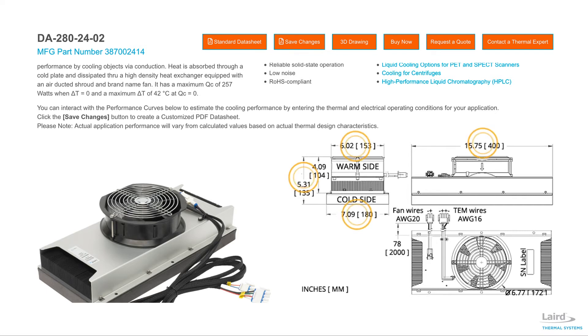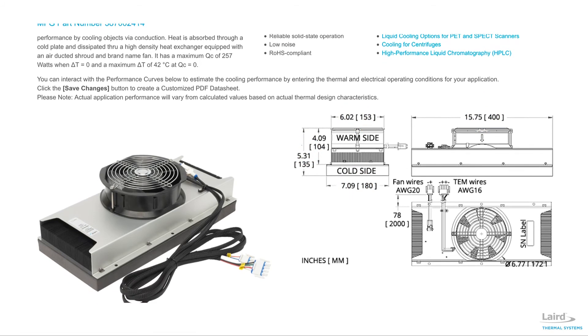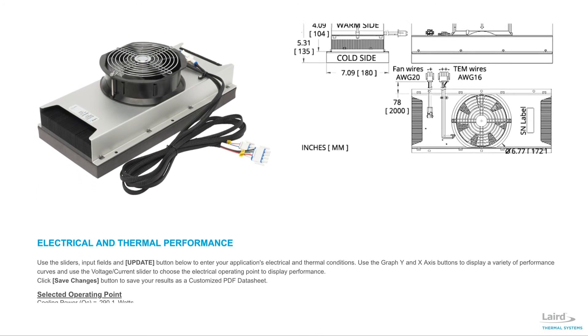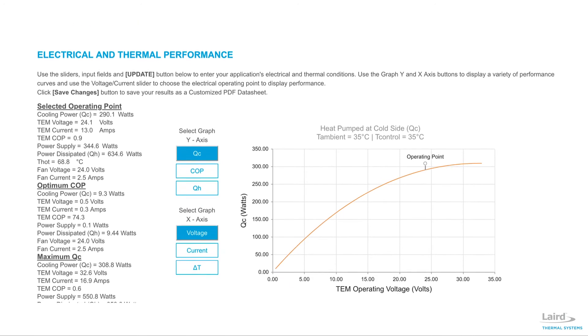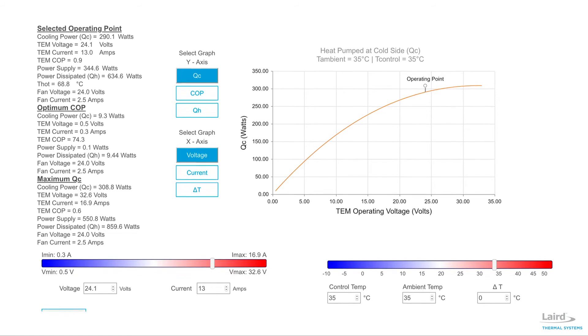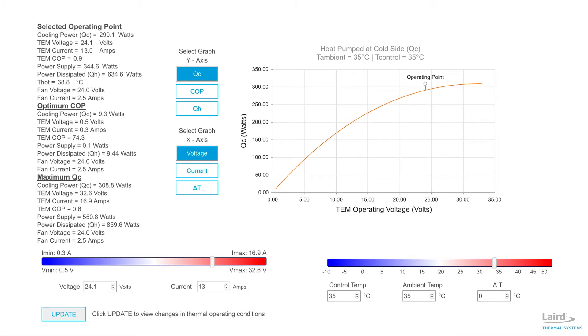First, we can check that the mechanical dimensions of the part will fit in our application. Next, we can turn to the tuning of the thermal performance and make certain the DA 280 24-02 meets application requirements. We can check that the cooling power of the DA 280 24-02 meets the 240 watt cooling requirement at the specified temperature of 20 degrees C. This is done by changing the control temperature and the ambient temperature to 20 degrees C and then clicking the update button.